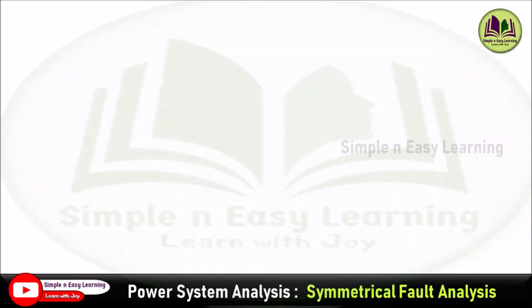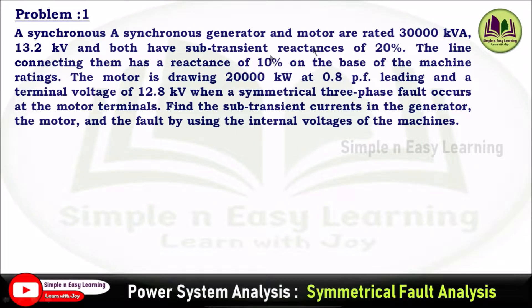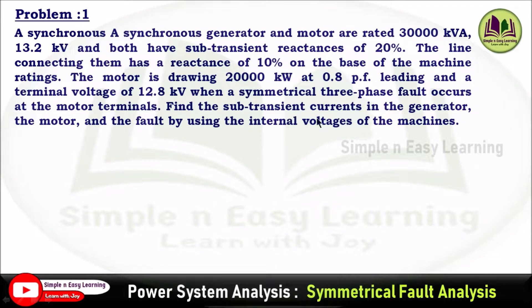Fault analysis using Thevenin's theorem, solved problem number 1. A synchronous generator and a motor are rated 30,000 kVA, 13.2 kV, and both have sub-transient reactance of 20%. The line connecting them has a reactance of 10% on the base of machine rating. The motor is drawing 20,000 kW at 0.8 power factor leading and a terminal voltage of 12.8 kV. When a symmetrical three-phase fault occurs at the motor terminals, find the sub-transient current in the generator, the motor, and the fault by using internal voltages of the machines.